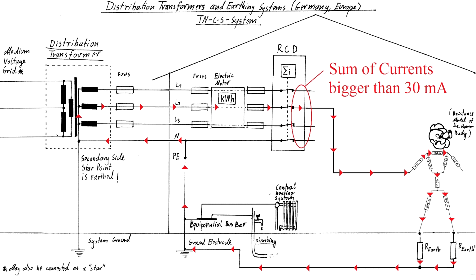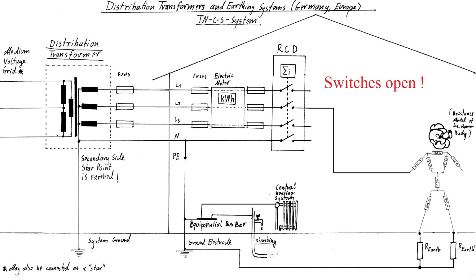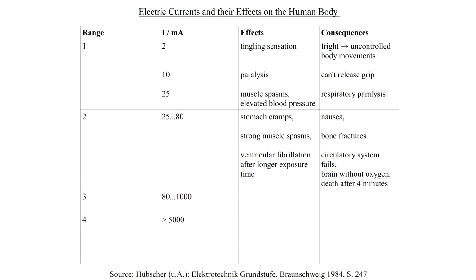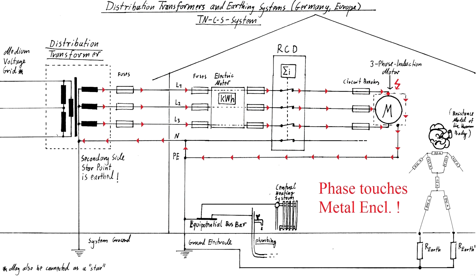This should ideally happen so fast that ventricular fibrillation cannot occur. But since we have seen that currents below 30 milliamperes can already be deadly, you should be cautious never to touch the phases directly anyway. But not always can you know if a part is under voltage or not. A typical fault would be this case, where one of the phases of a motor has contact to its metal enclosure. If it wasn't earthed and you would touch the motor's enclosure, it would be as if you hung directly on the phase.